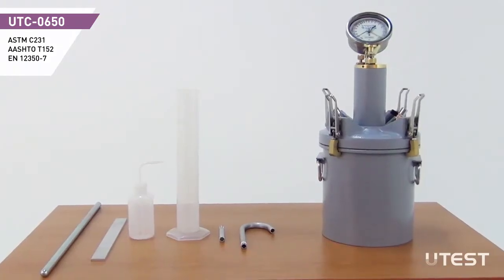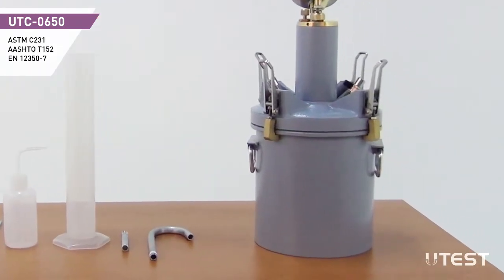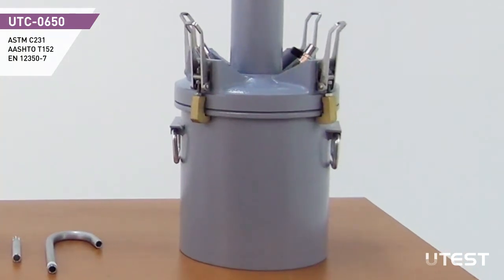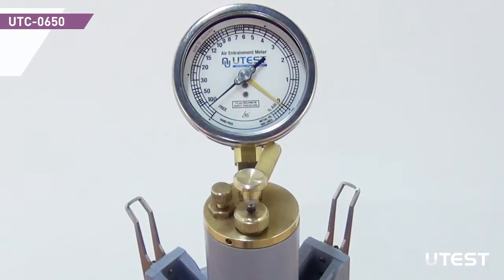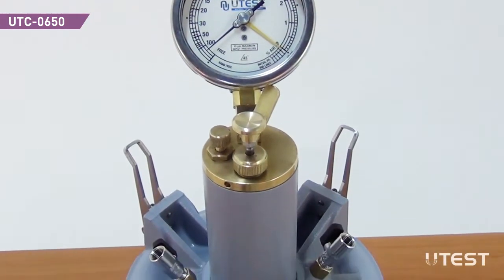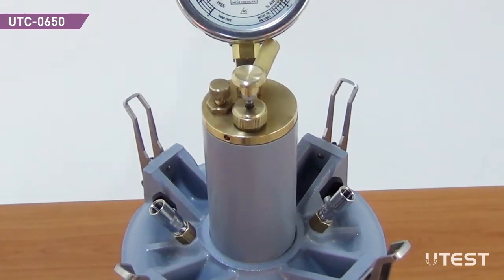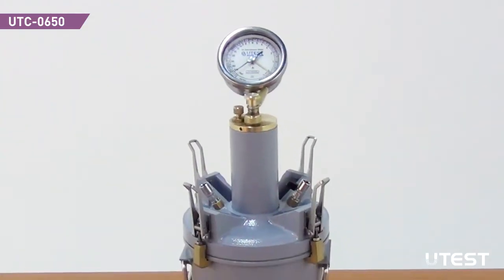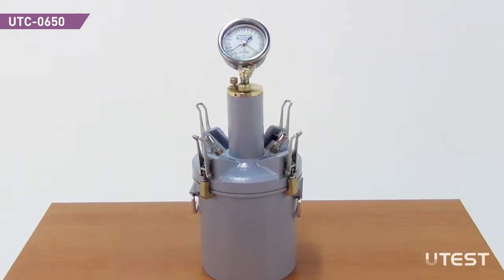The bowl also can be used for unit measurement of fresh concrete and aggregates. The meter measures up to 22% of entrained air. It is suitable for aggregate size of maximum 62 mm.